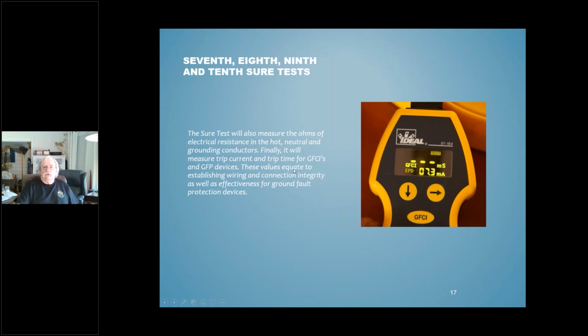And this one is showing me that I've got a GFCI that only tripped out at 7.3 milliamps, which implies that it's defective. I mean, a GFCI device that trips out at more than 6 milliamps is a defective device. You have to unplug it and then re-engage it to find out how many milliseconds it took for it to trip, which is another indicator of a problem if the trip delay is too long. This will also measure a 30 milliamp device, so pretty handy information.